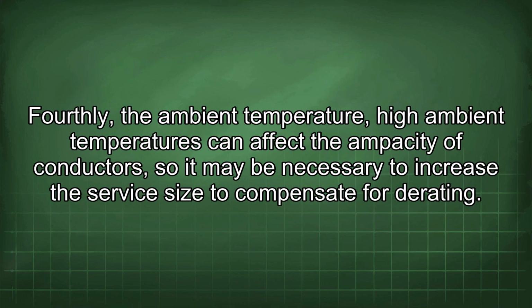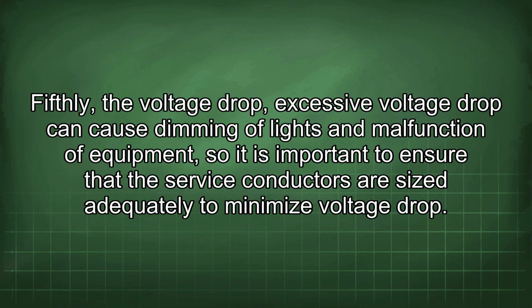Fourthly, the ambient temperature. High ambient temperatures can affect the ampacity of conductors, so it may be necessary to increase the service size to compensate for derating. Fifthly, the voltage drop. Excessive voltage drop can cause dimming of lights and malfunction of equipment, so it is important to ensure that the service conductors are sized adequately to minimize voltage drop.